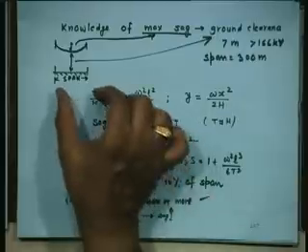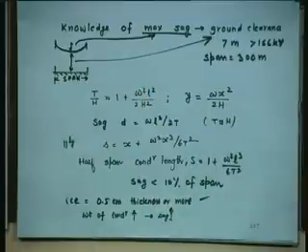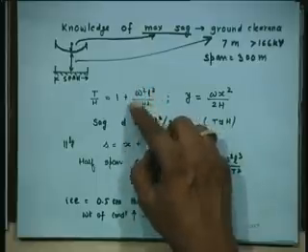The span is 300 meters. This is a span. Now, you can write these equations as we might have done earlier. T is the tension, H is the horizontal tension, T equals H times 1 plus omega square L square upon 2H square. Y is equal to omega x square by 2H, and sag is given by omega L square by 2T. T is roughly equal to H, so this quantity is very small.